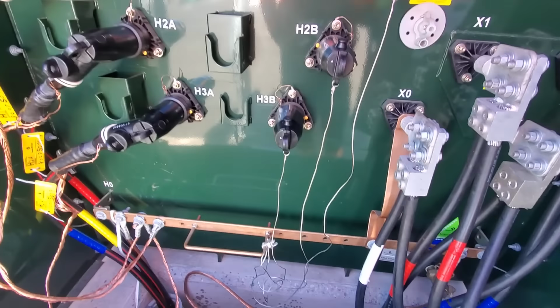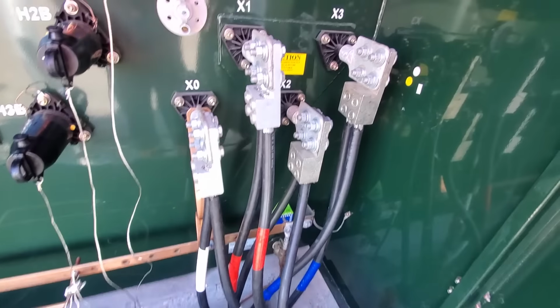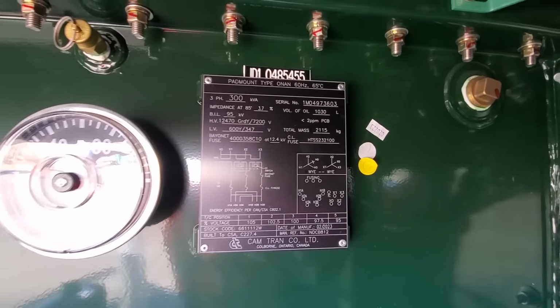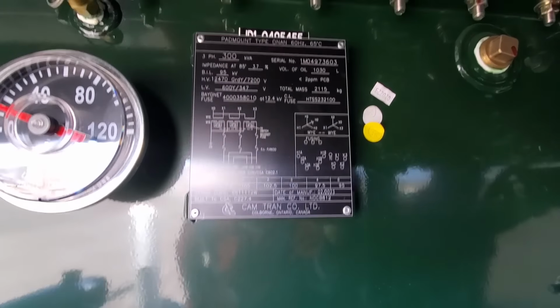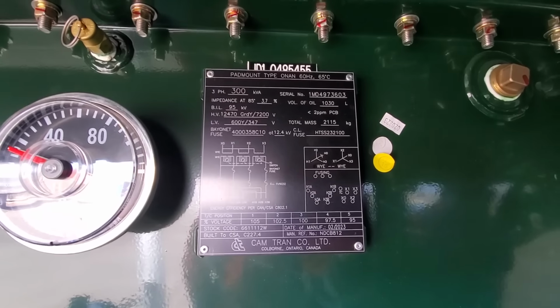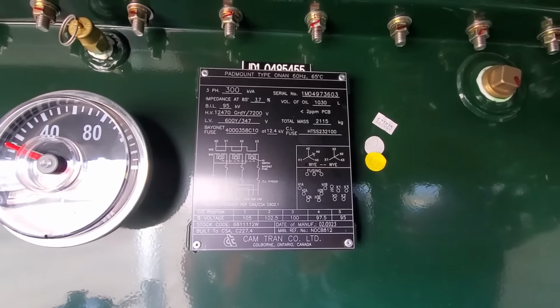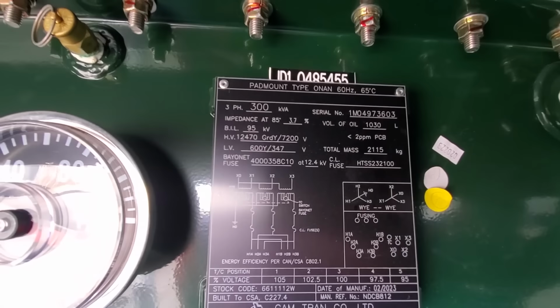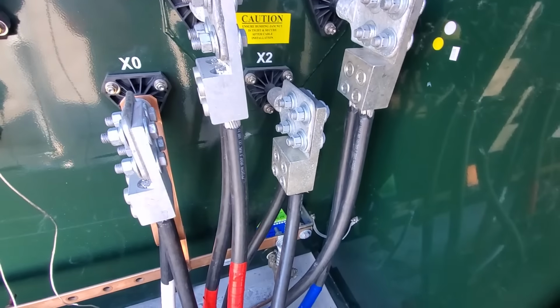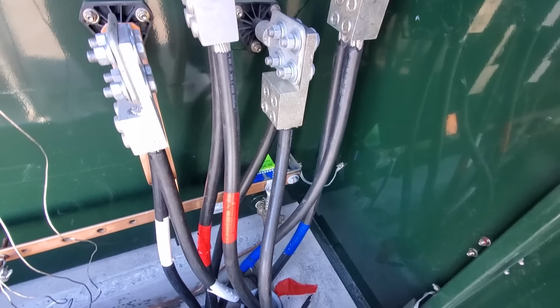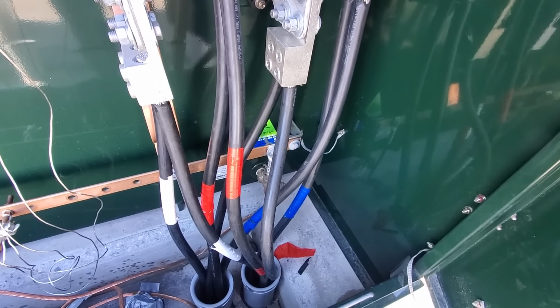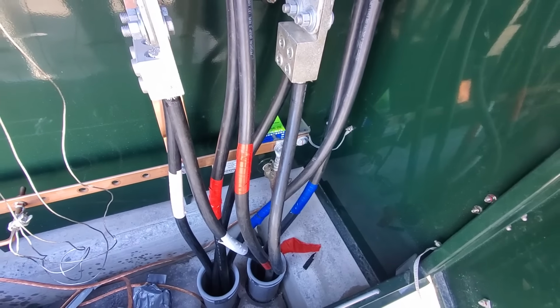So the boys did all this work yesterday. It's our transformer here, 300 kVA, 12470 phase to phase on the H1 side, and we've got 347-600 coming out on the secondary. There's not a whole lot of cables because of the 347-600 voltage. If this was 120/208, there'd be three times as many cables.